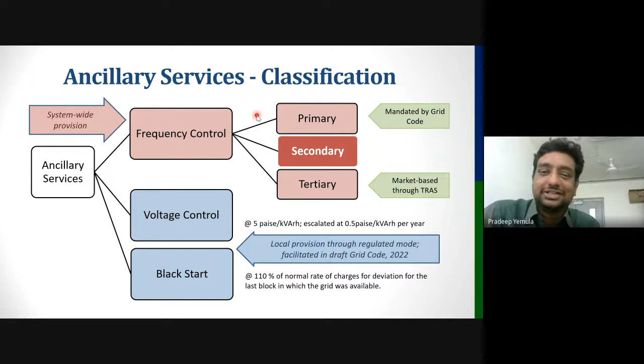This AGC is something different. AGC is different - in AGC, we do not control the governor, we control the load set point of the generator. We automatically control the load set point of the generator every 4 seconds from the control room in New Delhi to all the stations.